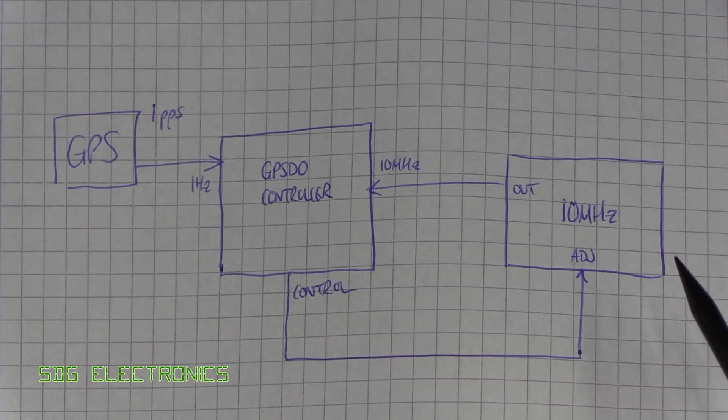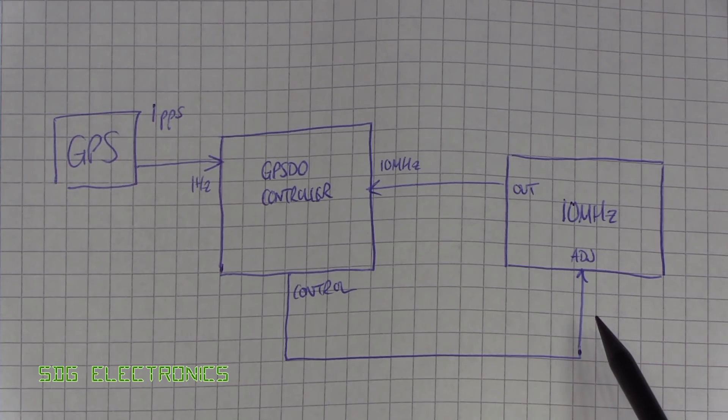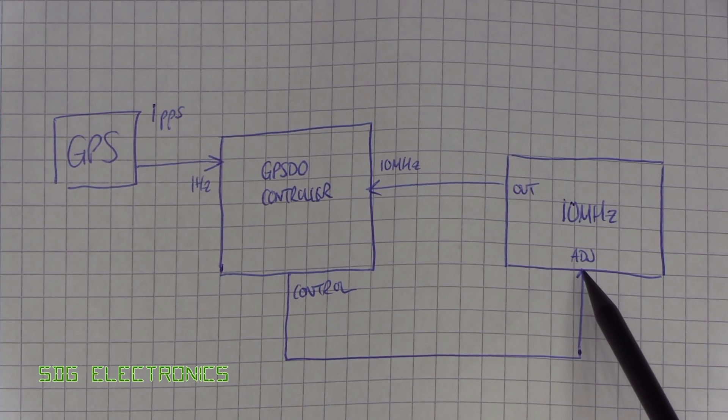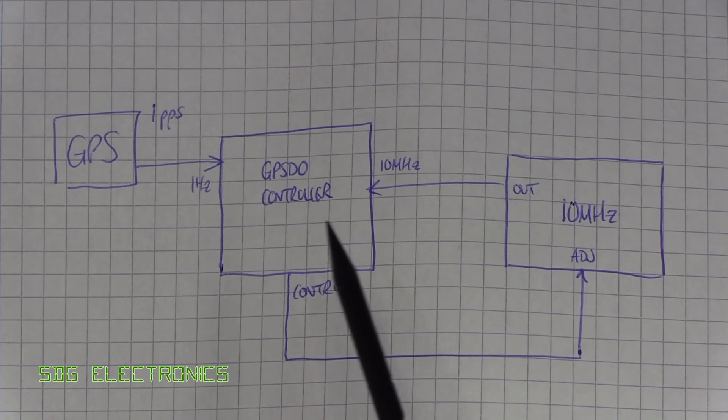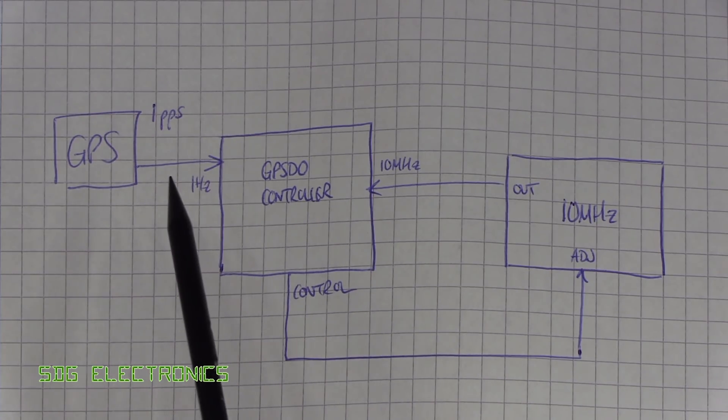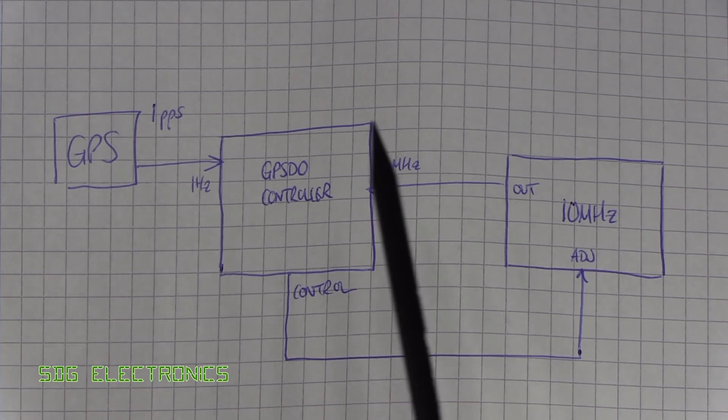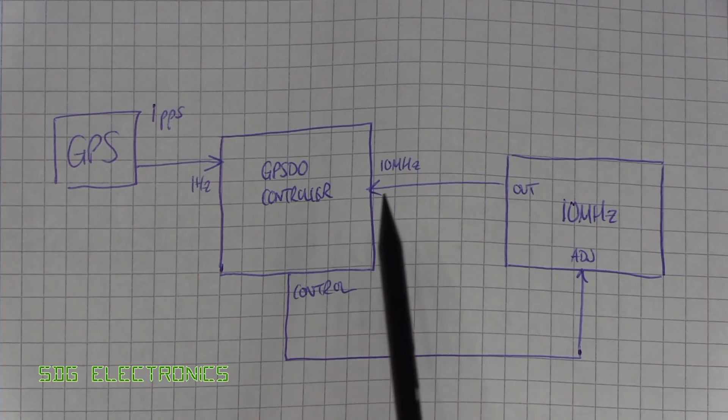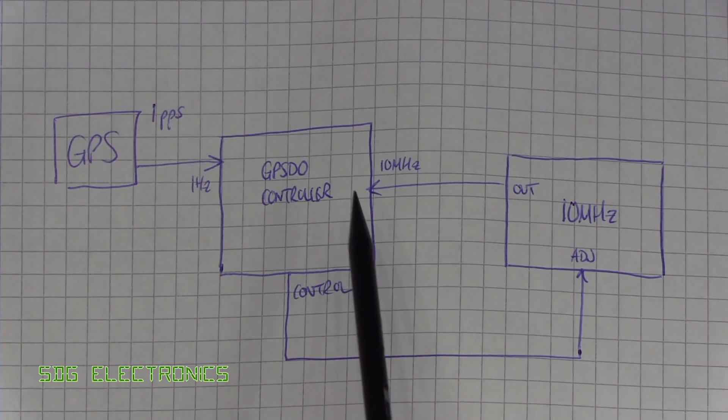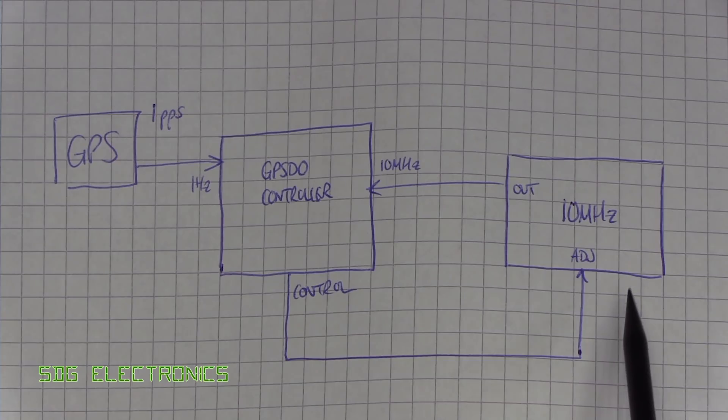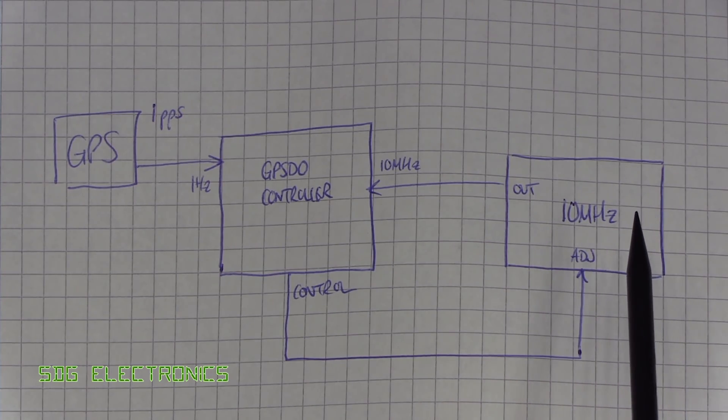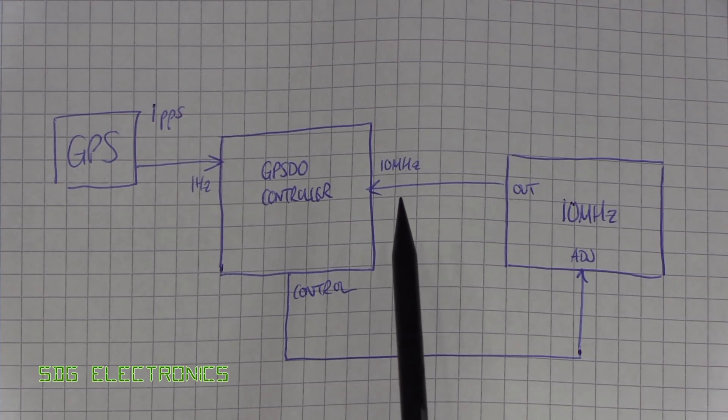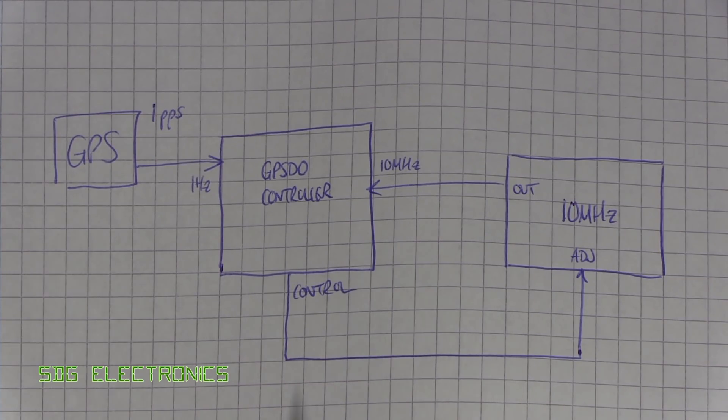Then we've got a 10 megahertz oscillator that has an adjustment pin or some way of adjusting the frequency on it. Then we have our controller in the middle, and what it's doing is looking at that one hertz signal, looking at the 10 megahertz signal and comparing the error, and then basically trying to control that 10 megahertz oscillator very finely so that it gives an exact 10 megahertz signal out.